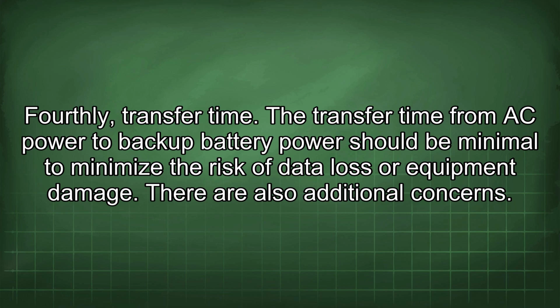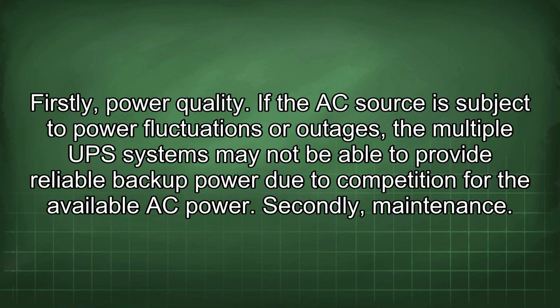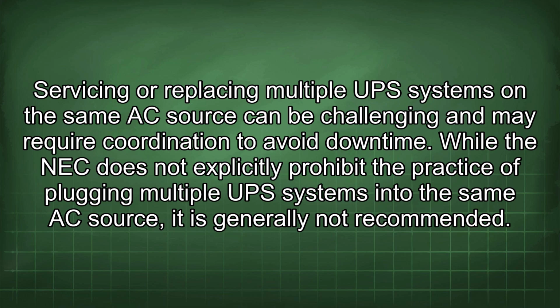There are also additional concerns. Firstly, power quality. If the AC source is subject to power fluctuations or outages, the multiple UPS systems may not be able to provide reliable backup power due to competition for the available AC power. Secondly, maintenance. Servicing or replacing multiple UPS systems in the same AC source can be challenging and may require coordination to avoid downtime. While the NEC does not explicitly prohibit the practice of plugging multiple UPS systems into the same AC source, it is generally not recommended.